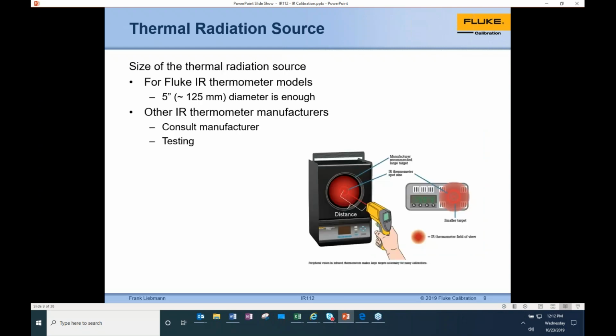using our IR gun. All right, so over the years, I've seen a lot of change or different styles of heat sources. We do have another line with smaller targets. With this one, we went with the bigger one. It was kind of a jump up. We do calibrate these to 17025. So again, we were trying to provide a heat source that is also a standard. So to achieve that, we went with the larger 5-inch targets. This gives you a really good range when it comes to distance to spot size, so you've got a lot of area to work with.